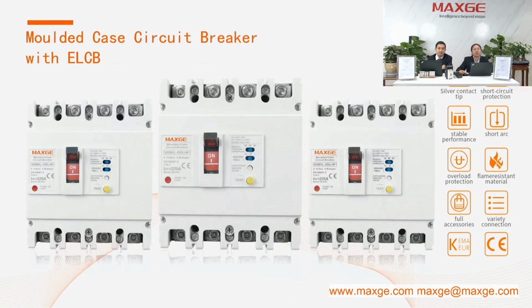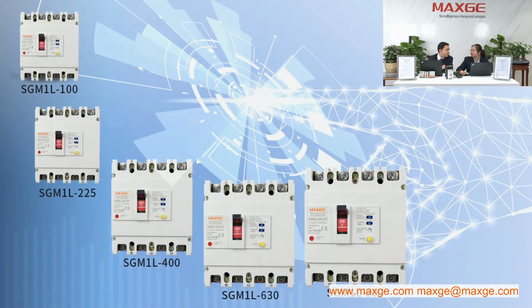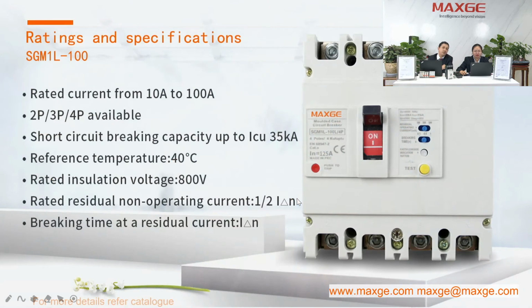Now next product is the MCCB with ELCB function. This is nothing but an RCBO. Yes, this also has the full range, starting from 100 to 800. Yeah, it has a complete three levels of protection. One is the overcurrent tripping, overload protection. The second one is short circuit protection, and third is the earth leakage protection.